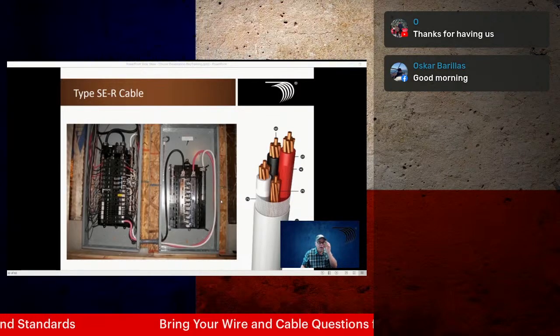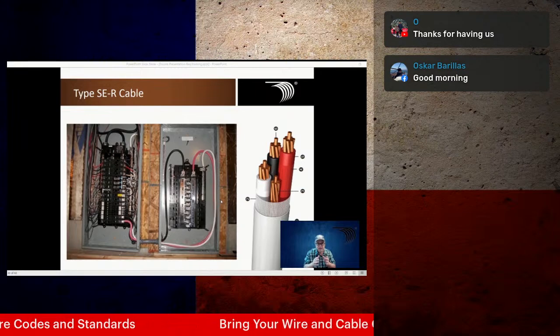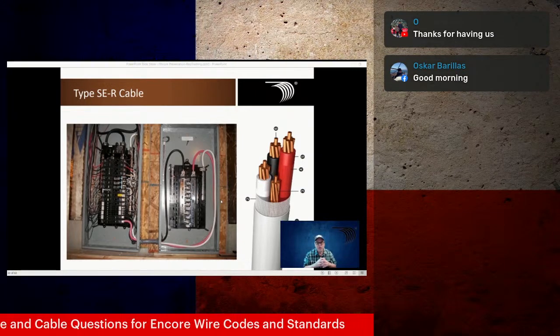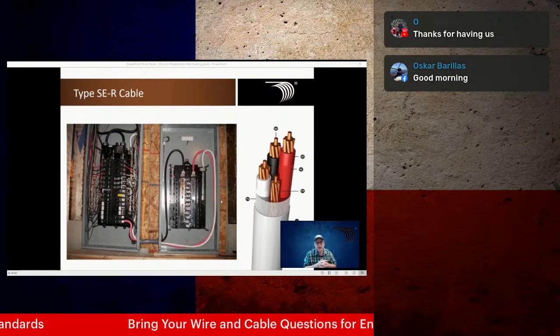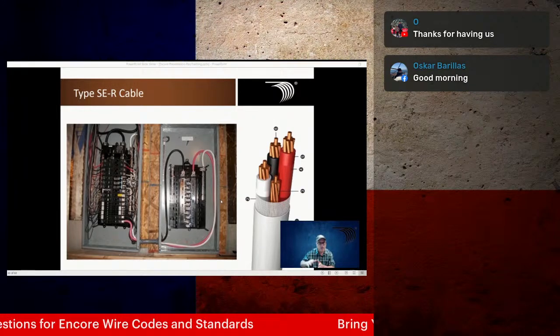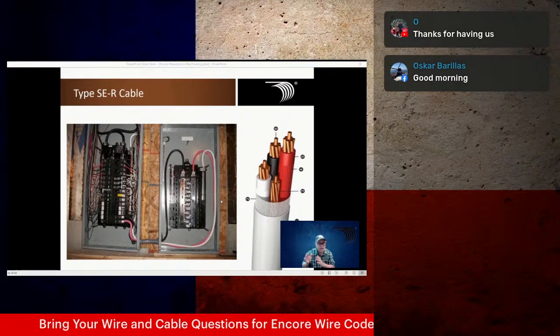And this is SER, typically what you're going to get downstream of your service panel as it goes to a remote distribution panel. Like in this case, the panel on the left is your service panel. The panel on the right would be your remote distribution panel. Just so happens that they're close together. And so you would use an SER once you go downstream, whether it's in the same building or a detached structure like a garage or outbuilding. Same concept. You would need 4 conductors.